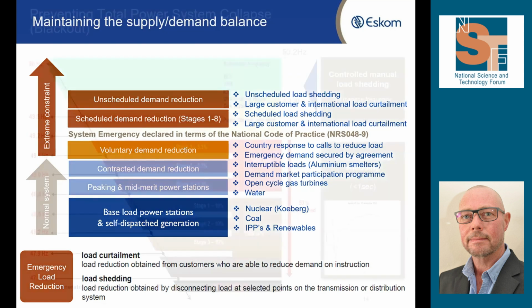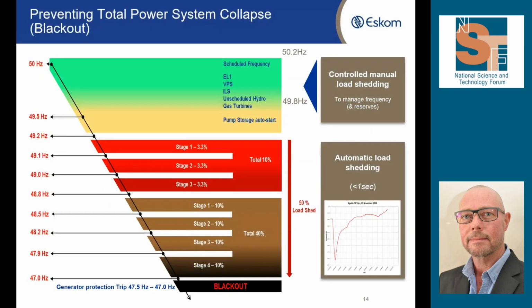Right, now, obviously, things happen quite quickly, as we saw last night. Within half an hour, we lost 2 very large generators, and that's what forced us to bring the load shedding forward to 1800 last night. But things can happen extremely quickly. We've had a number of examples over the years where we have lost an entire power station, so up to about 3,600 megawatts disappearing within less than a minute. Obviously, a human operator cannot react fast enough to try and mitigate against that. And so we have extensive protection schemes, particularly in the under frequency domain, where we can actually automatically remove customer load from the network and just try and stabilize it.